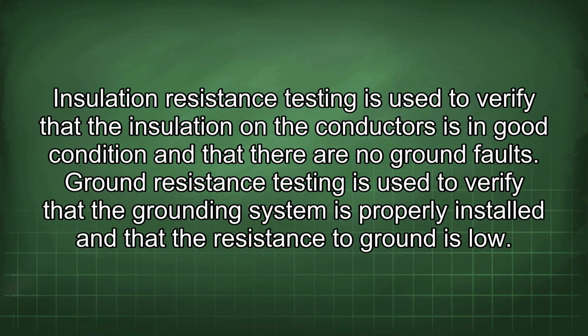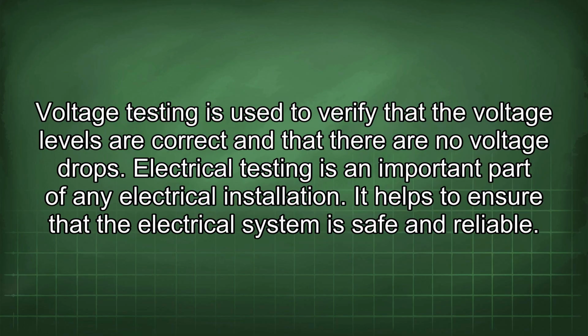Insulation resistance testing is used to verify that the insulation on the conductors is in good condition and that there are no ground faults. Ground resistance testing is used to verify that the grounding system is properly installed and that the resistance to ground is low. Voltage testing is used to verify that the voltage levels are correct and that there are no voltage drops. Electrical testing is an important part of any electrical installation. It helps to ensure that the electrical system is safe and reliable.